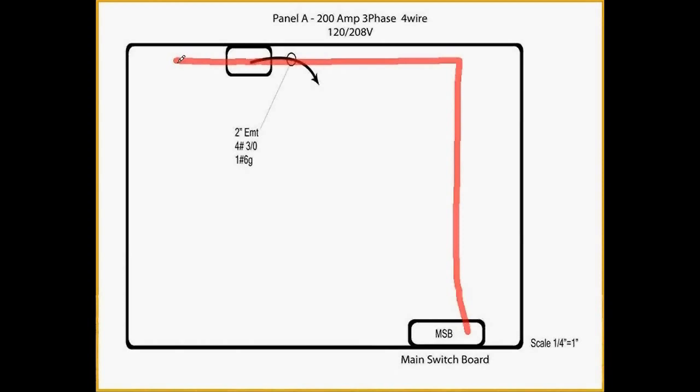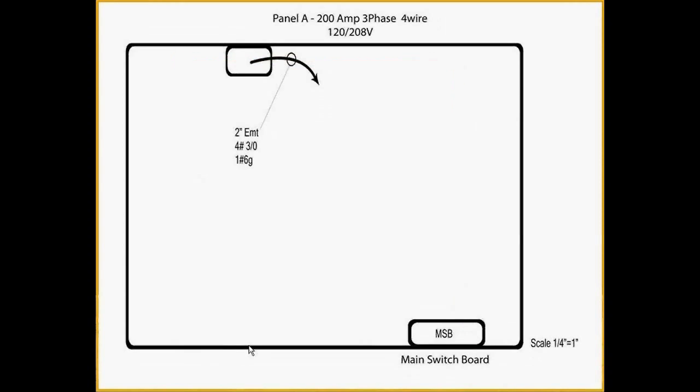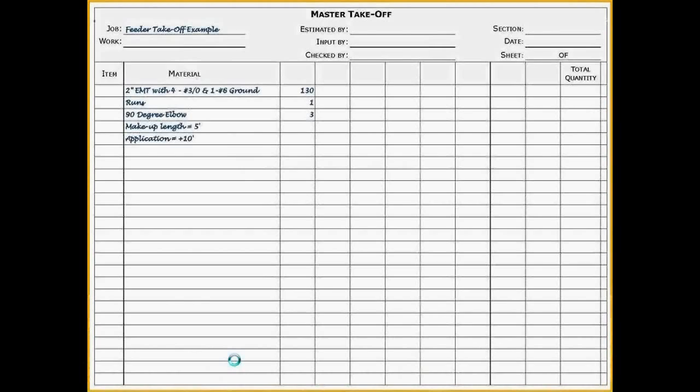I'm going to over roll slightly to cover the amount of conduit riser, which is the conduit going up or down out of panels. Since I'm using a virtual ScaleX and you cannot see the length it measured, in this example, I'm going to say that the ScaleX shows that this run is 130 feet long. I take this information and write it down on the takeoff sheet.